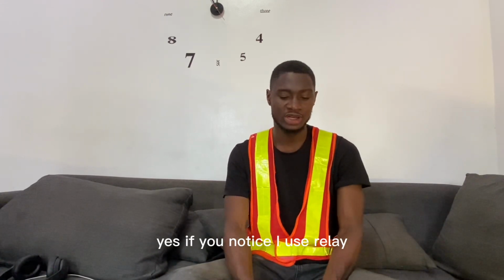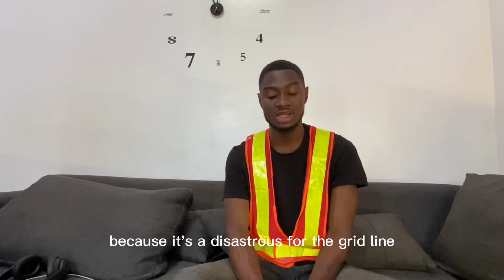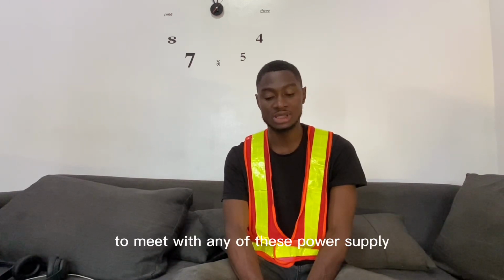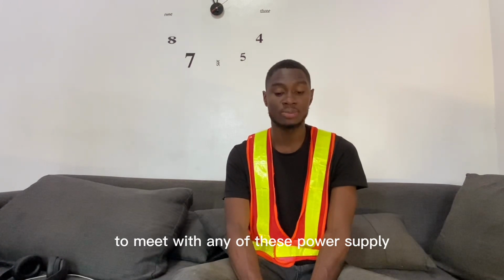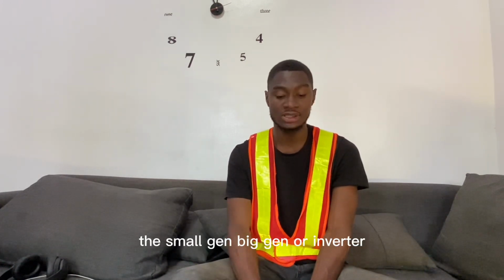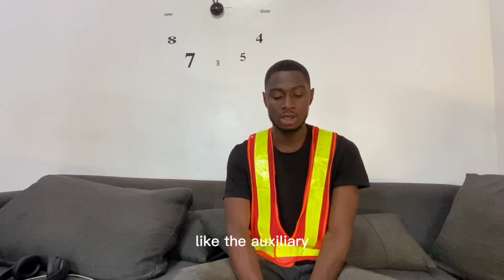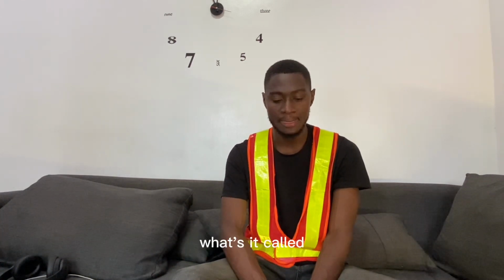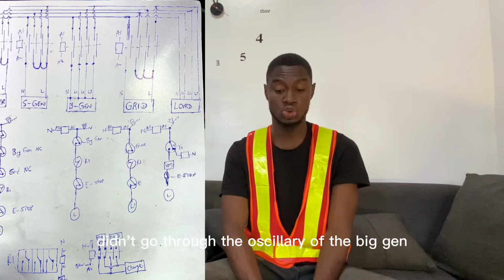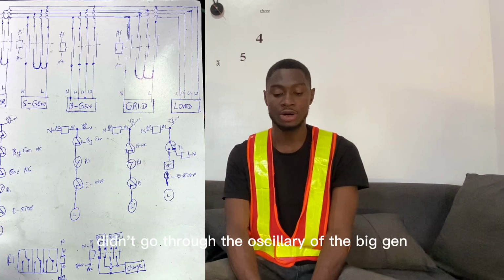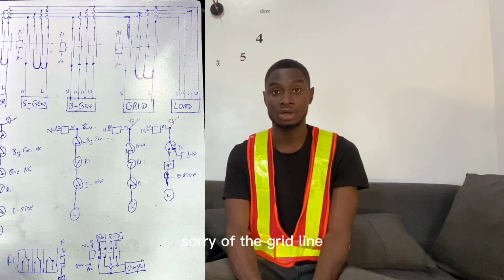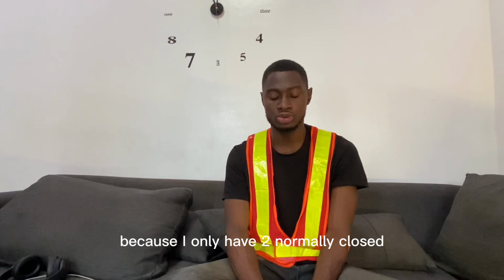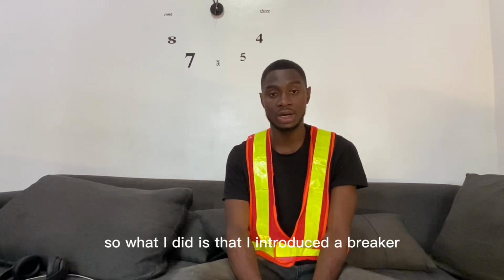If you notice, I use the relay and at the same time the auxiliary, because in case the relay fails, the auxiliary will be like a backup. It would be disastrous for the grid line to meet with any of these power supplies, the small gens, big gen, or inverter. So that's how I had to use both of them. Like the auxiliary, if you notice, the small generator didn't go through the auxiliary of the grid line, because I only have 2 normally closed. So what I did is that I introduced a breaker just to protect the coil or something.